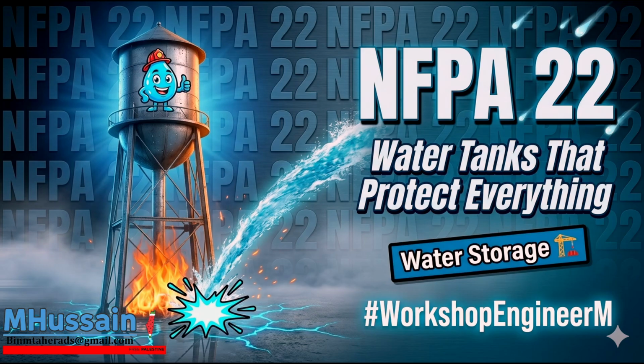Yes, they introduced specific separation distances between the fill lines dumping water into the tank and the suction pipes pulling water out. That was a much-needed addition to the code. Think about it. If your fill line is dumping a high-velocity stream of fresh water directly above or immediately adjacent to your suction pipe, that incoming column of water creates severe turbulence. It's churning everything up. It introduces millions of entrained air bubbles deep into the water column, and if the downward velocity of the pump suction is greater than the natural upward buoyancy velocity of those air bubbles, the pump will just inhale that air, which leads right back to cavitation and pump destruction, even without a vortex.